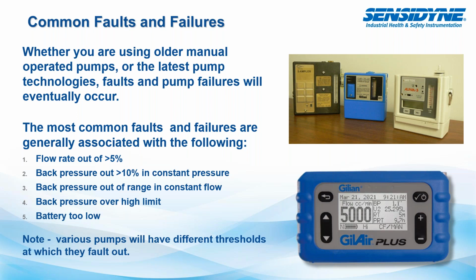And there's a reason that it does shut down when it does, even though it may still have a little bit more power left. I do want to note that mostly I'll be talking about Sensidyne pumps today, but even pumps from other manufacturers have their own set points. They may be slightly different in their thresholds at which they fault out, but in general, most pumps' thresholds are relatively within the same parameters.